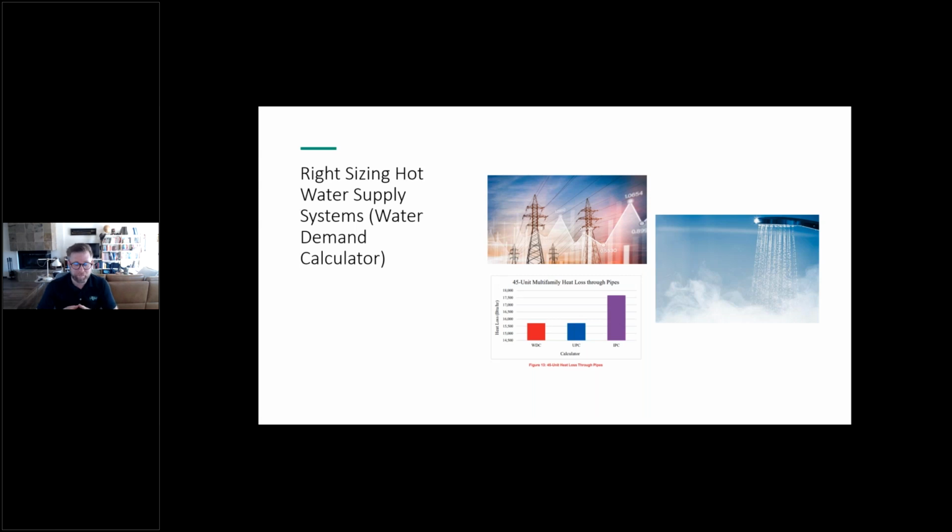And we were able to basically see that instead of sizing a building like a sports stadium at halftime, which is what the Hunter's curve assumes, that kind of congested flow rate, we looked at real world data and realized that we could go much smaller. We had better probability values, or P values. Now, when you look at Hunter's curve, the question often comes up, oh, well, we adjusted for flow rates and more flow efficient fixtures. That's just the Q value, the flow rate through the fixture. But the fixture unit is a value of probability and flow rate. So the probability of that fixture being on at the same time as other fixtures.